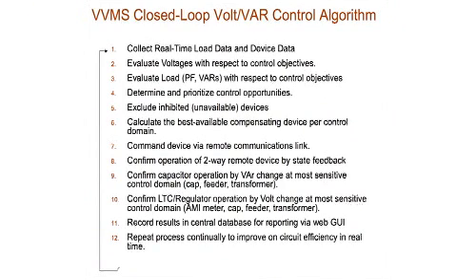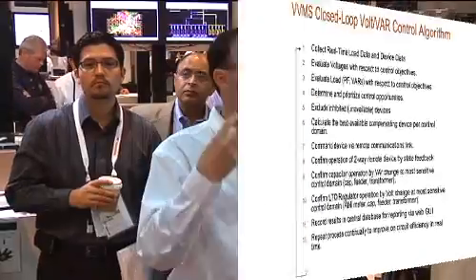We issue a command to that device to operate, either to step the transformer or to close or trip a cap, and then we monitor that device to ensure that the operation succeeded. And that's part of a failure analysis, important to make sure that we identified the cap or LTC operated correctly. We also then monitor the head of the feeder to make sure we see the VAR effect, or the voltage effect at the head of the feeder, to make sure, A, that cap did operate, and it did operate on the correct feeder. And that's the closed loop aspect that we're talking about. And then we log the results to allow reporting at a later time for post-analysis.